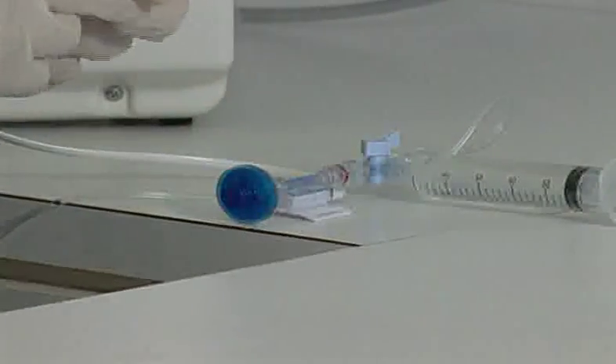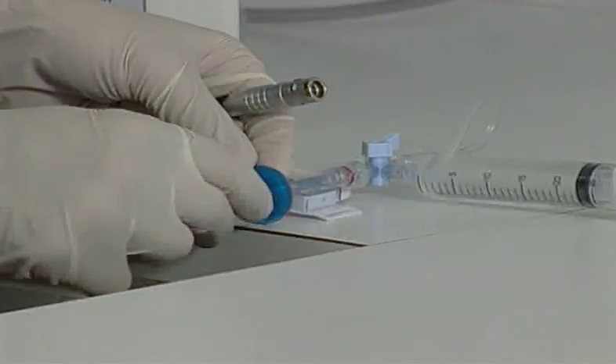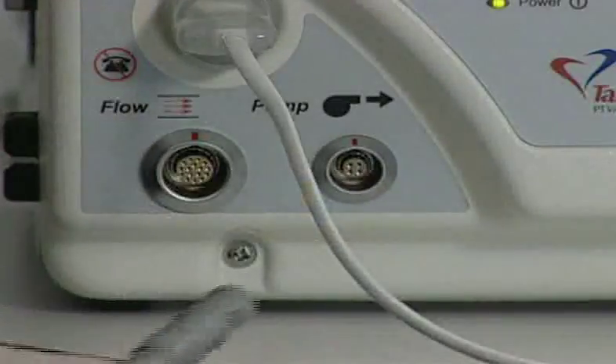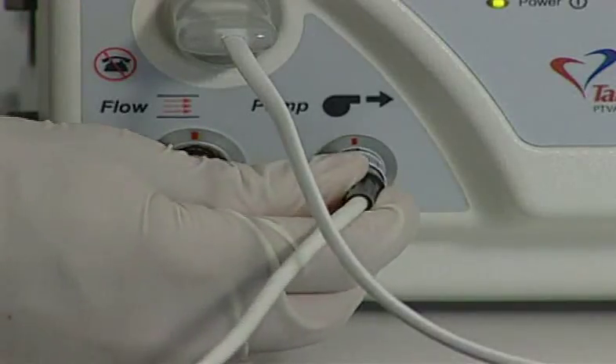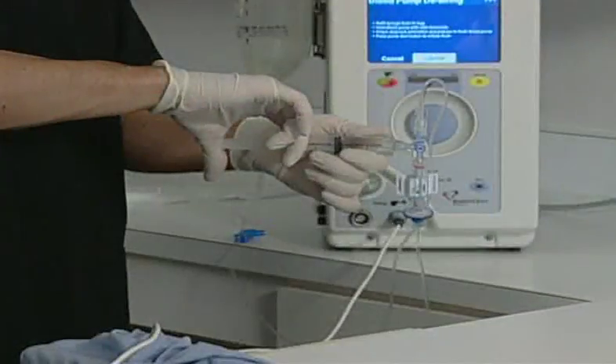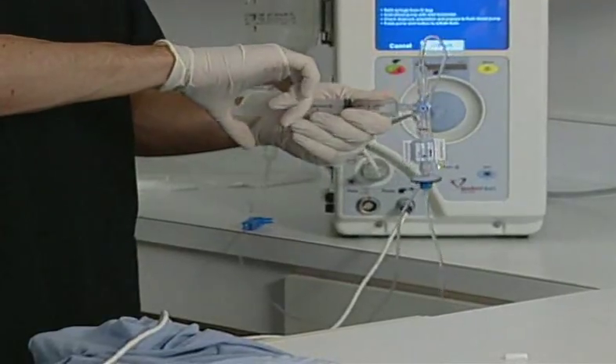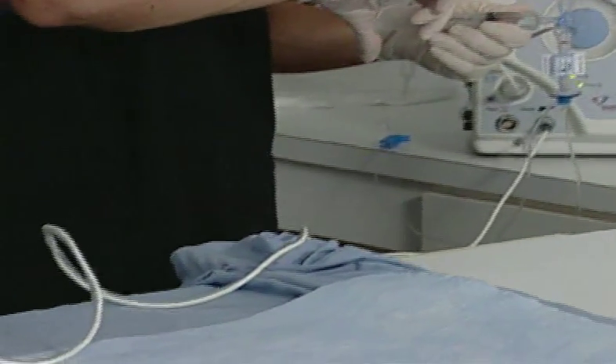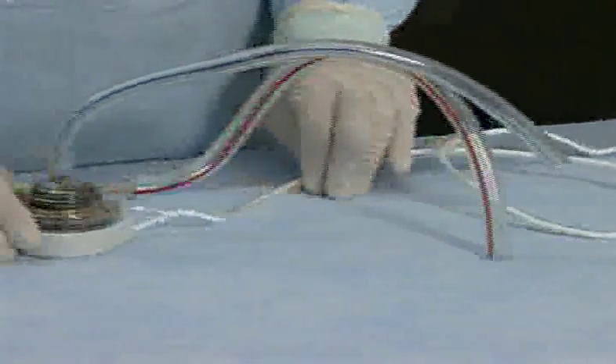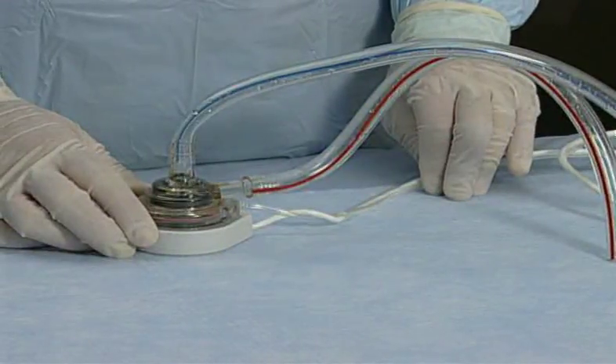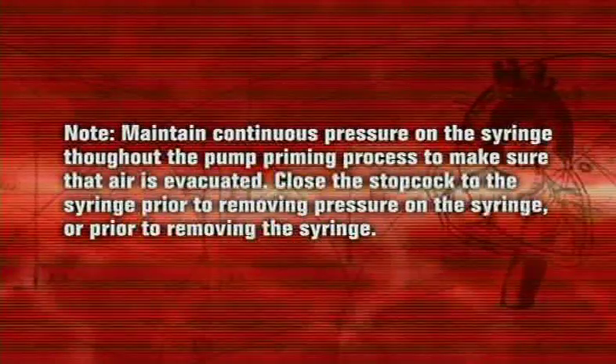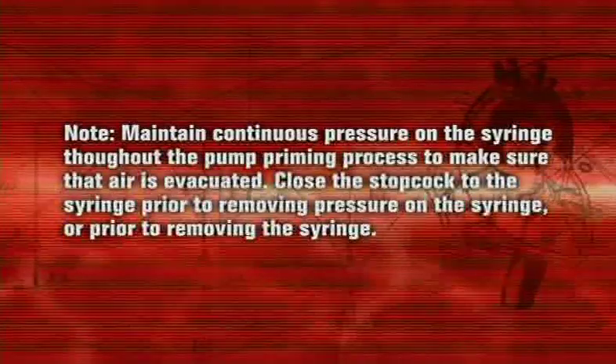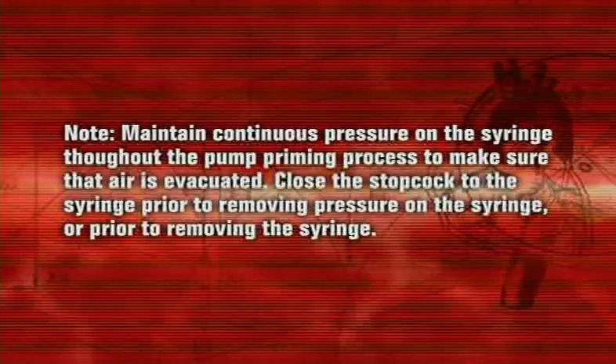The controller operator then connects the pump's infusion line to the bacteriologic filter at the end of the infusion assembly and connects the pump power line to the pump power receptacle on the front of the controller. The controller operator slowly injects 15 cc's of heparinized saline into the pump infusion line to prime the lower housing of the pump. This will gradually fill the pump's lower housing. Note: maintain continuous pressure on the syringe throughout the pump priming process to make sure that air is evacuated. Close the stopcock to the syringe prior to removing pressure on the syringe or prior to removing the syringe.